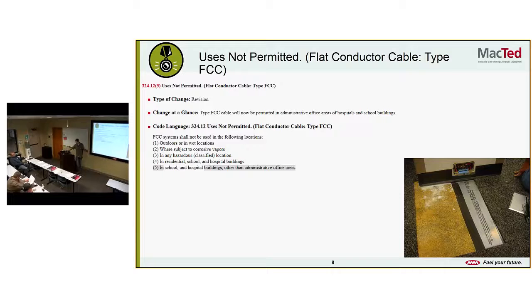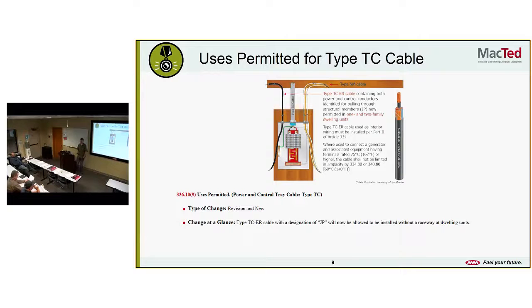Uses not permitted, flat conductor cable, type FCC. I've never worked with this stuff. Looks like it goes underneath the carpet tiles. You guys use this stuff at all? Have you used it? There's a revision: type FCC cable will now be permitted in administrative office areas of hospitals and school buildings. It is not permitted outdoors or in wet areas, areas subject to corrosive vapors, any hazardous locations, or in residential, school, or hospital buildings other than administrative offices. So that's what they added. It used to just say you couldn't have it in a school or a hospital. Now they're saying you can use it in the administrative areas of a hospital and a school. Run that stuff right underneath the carpet. It sounds like it'd be pretty easy. No, it's a pain in the ass. Well, maybe it's not that easy.